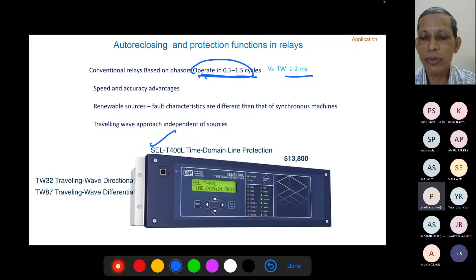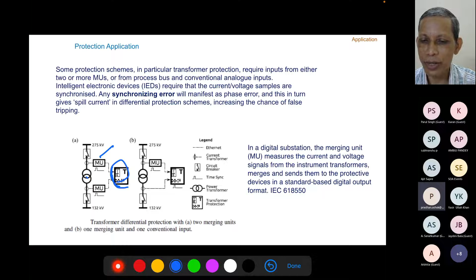Applications of traveling wave protection, which are independent of the sources, give better scope and better performance or reliability of the system. Substation technology is changing with merging units, so a transformer protection scheme may use different merging units. These merging units use different time information from their own atomic clocks, which must be very accurate and precise, otherwise it will create problems.